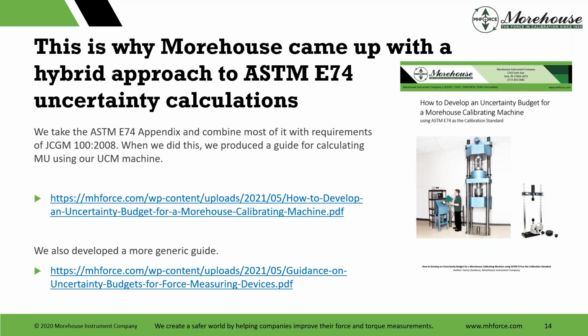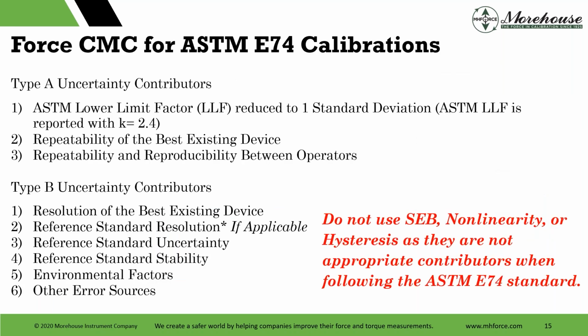And this is how I want to do my budget. So I recommend the one at the top for most people if you really want a really good analysis of uncertainty. And that one at the top starts with things like this. I'm going to break my uncertainty down into typically type A and type B uncertainties. And my type A, that one on top, should have a lower limit factor reduced to 1 standard deviation, and the ASTM is reported with a K value of 2.4. So when I reduce that, you get a certificate, it says, hey, your load cell was calibrated by X, your lower limit factor is this. You reduce that out to divide that by 2.4.